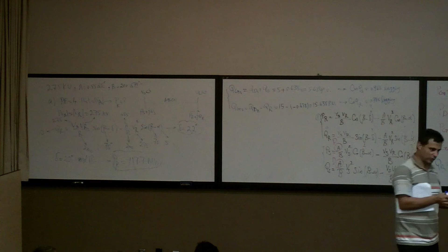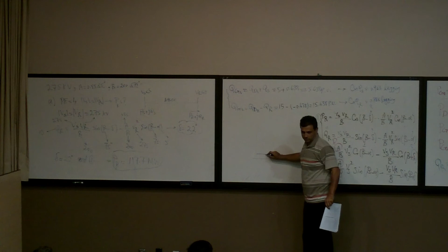The main difference between a synchronous condenser and the capacitor is that the capacitor is discrete. If you put this much capacitor, the Q is going to jump. It's not going to be continuous. You know what I'm saying? For example, your Q is going to change like this. If I put this much capacitor, I have this much Q. If I put this much, I have this much Q. This much Q, this much Q. But the synchronous condenser, you can do it this way, continuously. You can select any number, which is much more expensive than the capacitor.